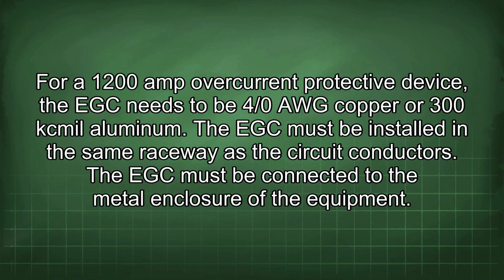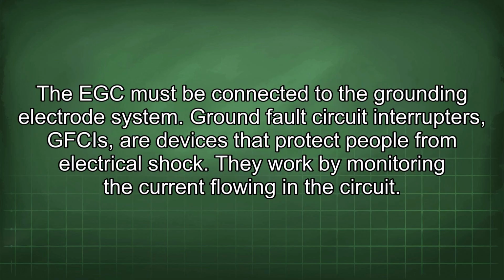The EGC must be installed in the same raceway as the circuit conductors. The EGC must be connected to the metal enclosure of the equipment. The EGC must be connected to the grounding electrode system.